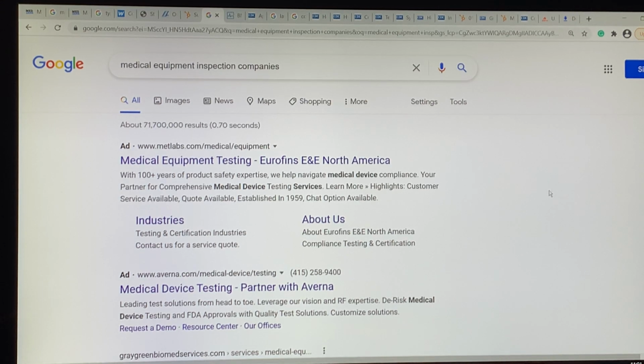They're going to come in, they're going to test your autoclave. They're going to test your endoscope. They're going to test your suction. They're going to make sure all the calibrations are right on your meters, your oxygen, and on the anesthesia cart. So the defibrillator, everything, that's what they do.